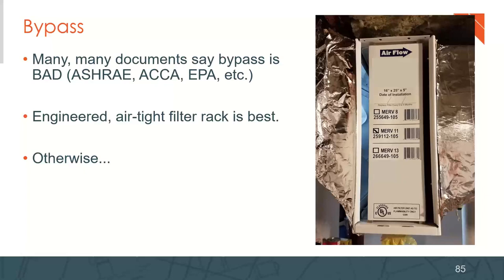And then the last thing to say is about bypass. Bypass refers to air moving around a filter instead of through it. You can see that this engineered airtight filter rack is a great way to go, because the filter is filling this entire air, well, not in this image. In this image, there is significant bypass around it, right?